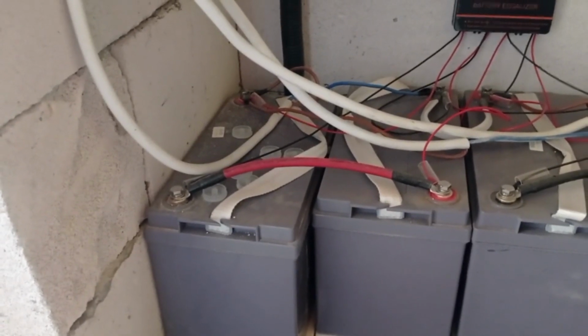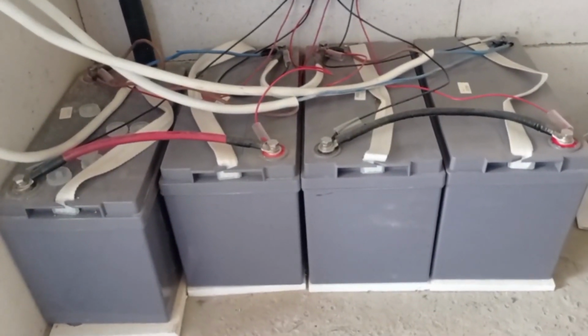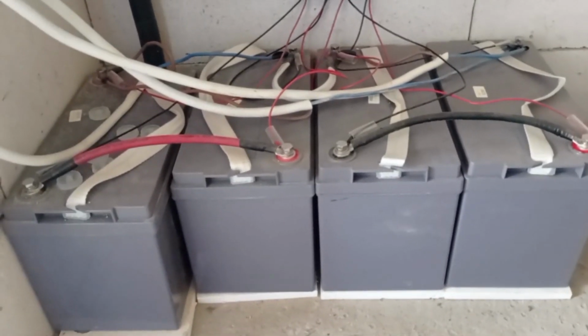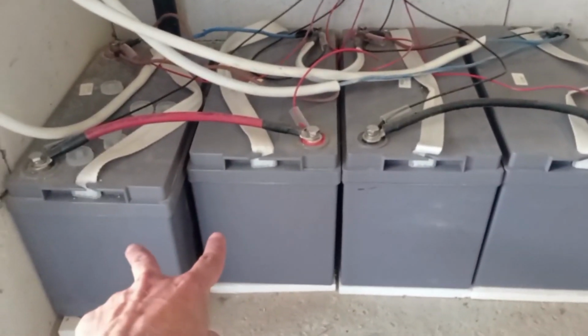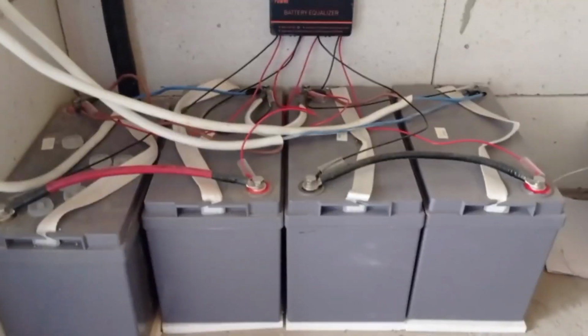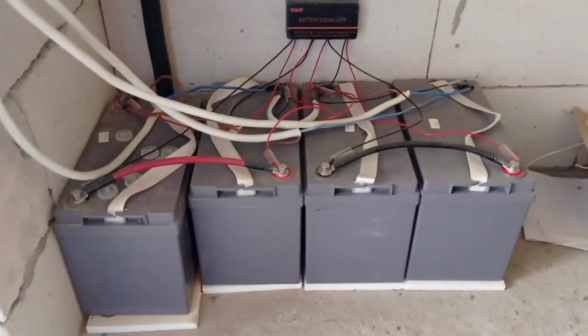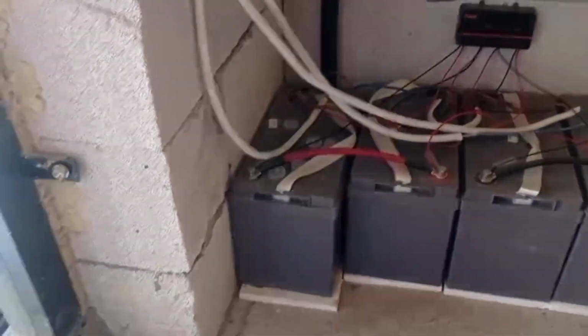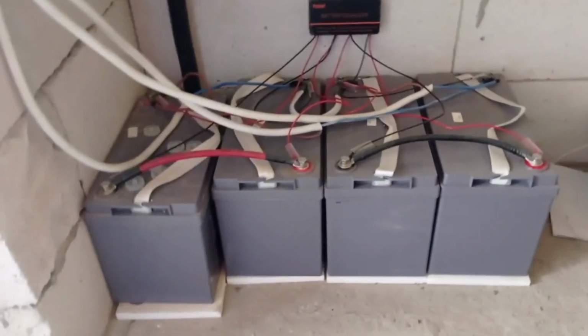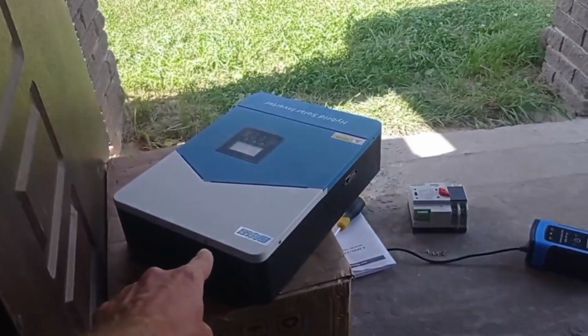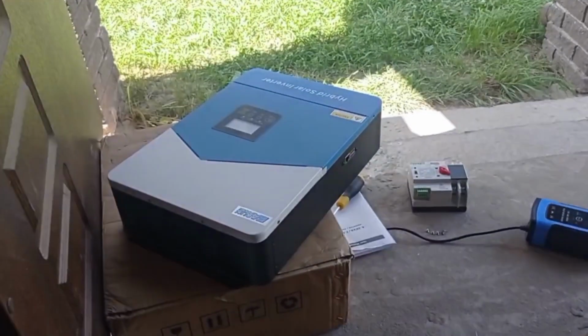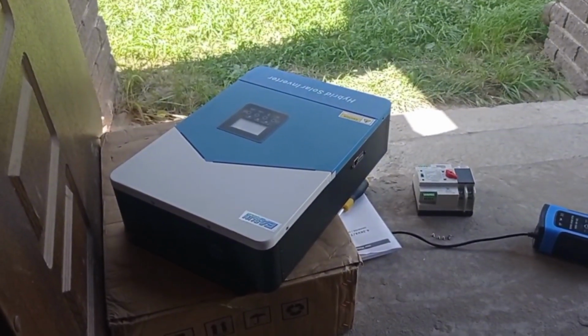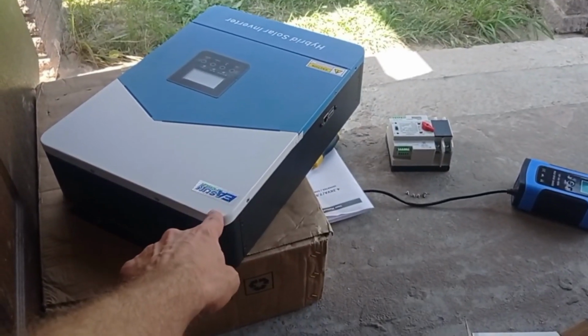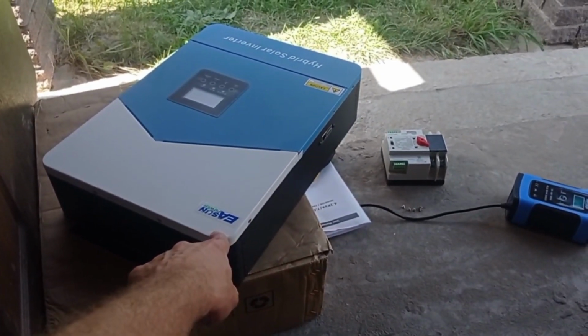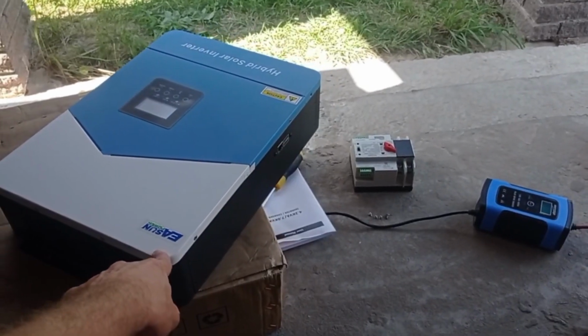Then you have the 24 volt battery bank, or go for a 48 volt battery bank, for example this one. That's the cheapest solution, but the problem is that these cannot accept too much current on charge and discharge, 30 amps is their limit, unless you want to blow them off. That's reality, so this one is by default limited to 30. In the settings, of course, you can change it, but it can accept up to 80 amps. This exact version, the 48 volt one, is for 6.2 kilowatts of power.